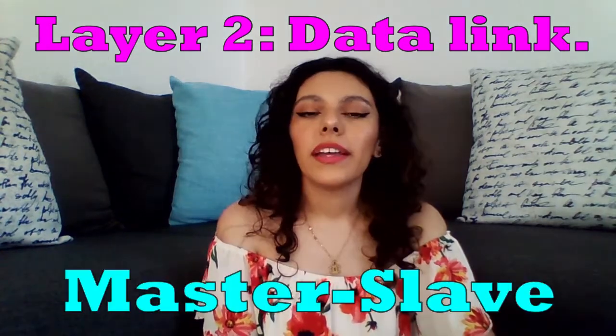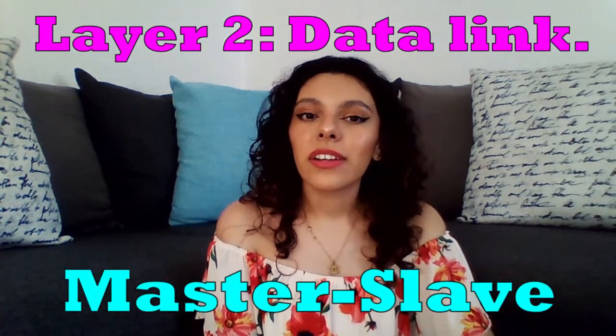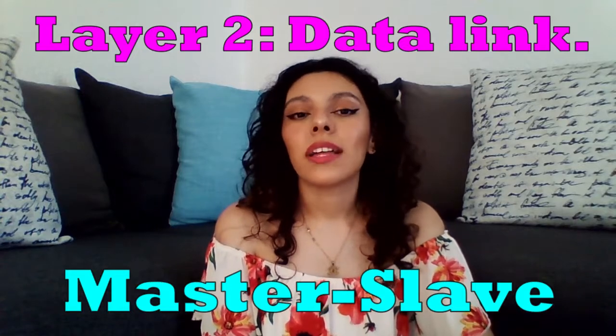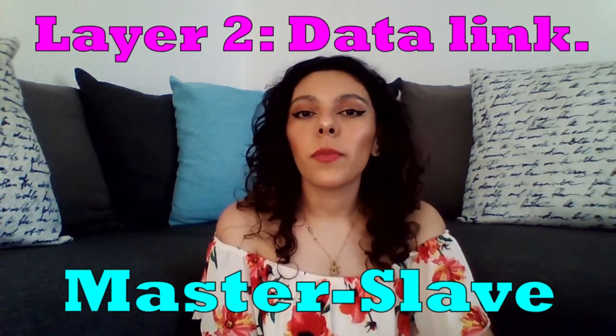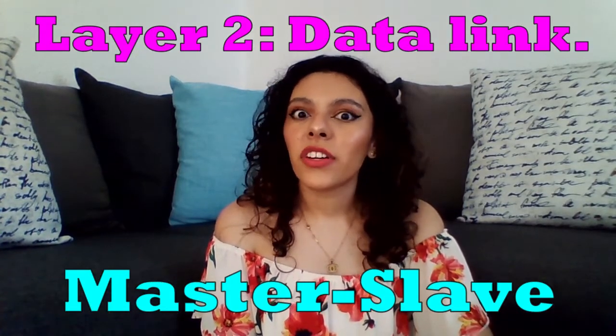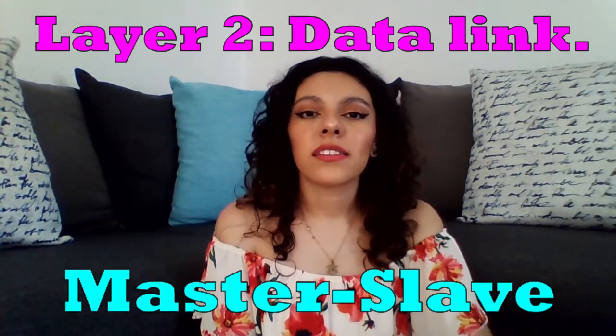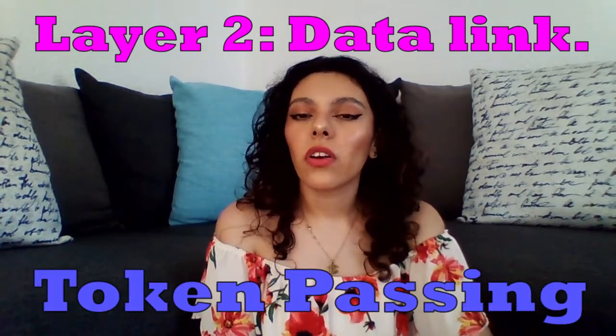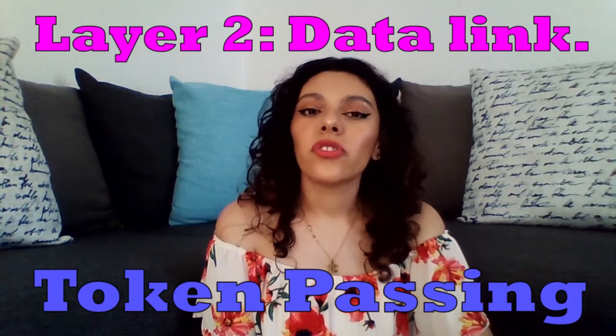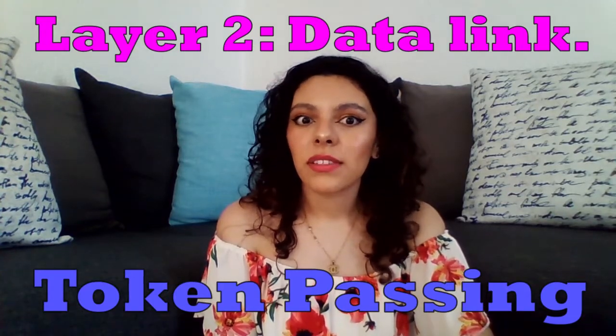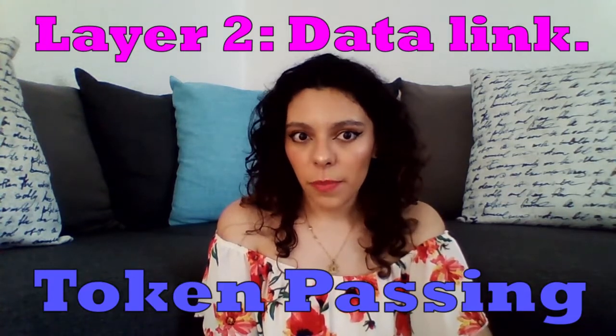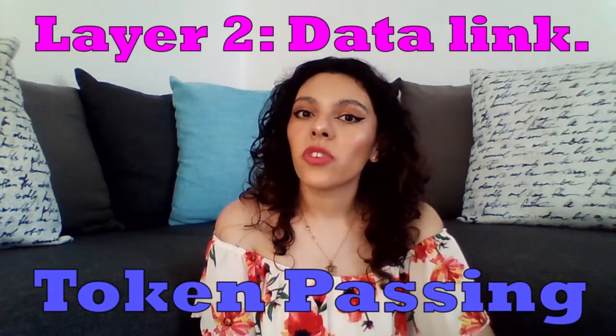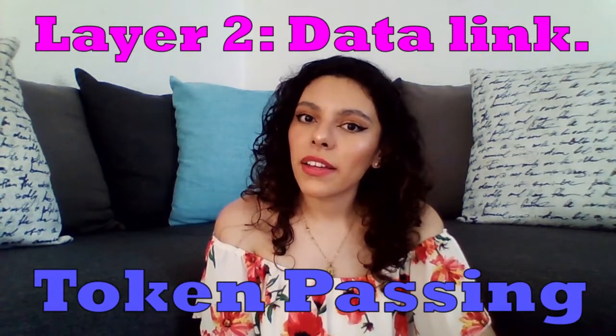Layer 2, which is the data link, uses the FDL system, which combines the master-slave methodology with that of token pass. In the master-slave method, the master sends a request to the slave so that they, in turn, send the information requested. The masters are generally controllers, and the slaves are sensors and actuators. The token passing method ensures that not all participants send data to the network at the same time, and only the devices that have the token at the time can send data packets to the network.